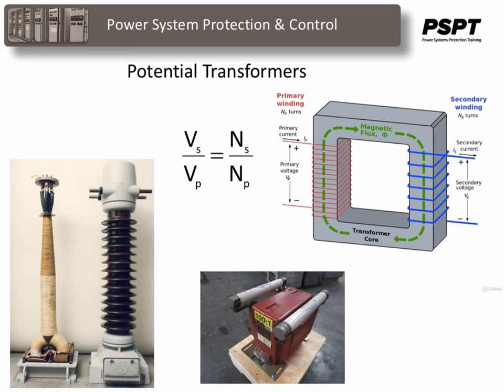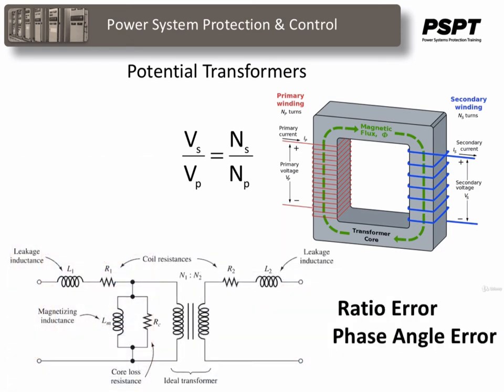The net result is that the secondary voltage is slightly less than the ratio of the turns would indicate, and there's a slight difference in the phase relationship. These two errors are called ratio errors and phase angle errors, and may be represented by the transformer equivalent circuit. Now, I mention this, not that it's necessarily typical of only potential transformers. All transformers have these errors introduced into them because of nonlinearity and magnetization current.